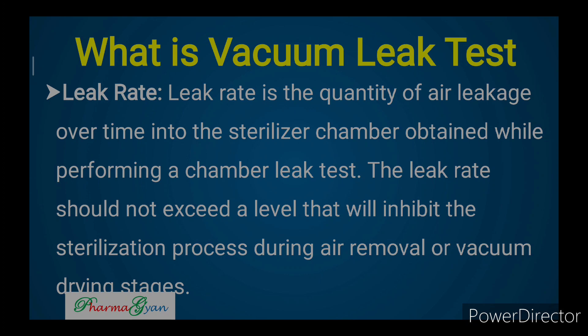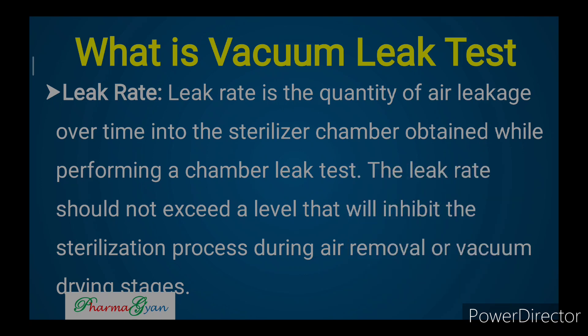Leak rate is the quantity of air leakage over time into the sterilizer chamber, obtained while performing a chamber leak test. The leak rate should not exceed a level that will inhibit the sterilization process during air removal or vacuum drying stages. It is a pre-determined quantity — for example, leakage should not be more than a defined value per minute or per 10 minutes. The defined limits and acceptance criteria will be discussed further in the video.